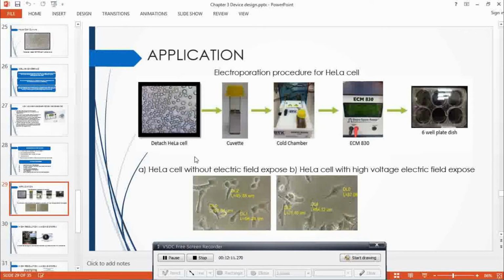So what we do with the system is, for example, if we have the cells, you detach the HeLa cells, include the cells in the cuvette, put it in the chamber, and then excite the cells with the ECM 830 generator. That means we are passing a voltage ranging from 5 to a few thousand volts through the cells. This is called electroporation. Basically, you excite the cells with an electric field, either high voltage or low voltage.